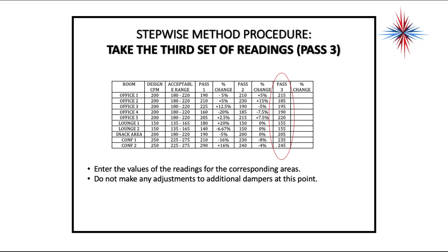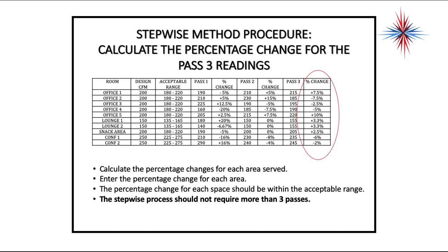Take all readings for Pass 3 without making any adjustments, then calculate the percentage of change. One location — Office 5 — is at 10%, which is right at the margin of error. If this were my customer, I'd probably pull that down just a little bit, but not much — I don't want to affect anything else badly. The stepwise process should not require more than three passes. If you do this correctly, three passes is all it takes, as long as you have enough airflow to start with.